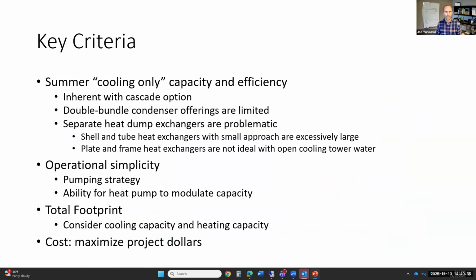So one of those factors is the double bundle that Colin mentioned. The manufacturers weren't willing to commit to that. So those strategies that employed or that could have employed that were kind of not on the table anymore. That's because the efficiency and the cost to get rid of excess heat in the summer for those options would just be pretty bad. So we ended up going with the Cascade option. And I'll show that on the next page in a second.